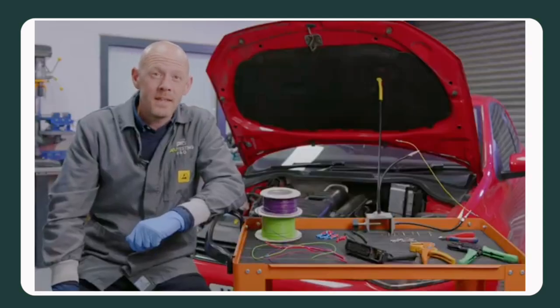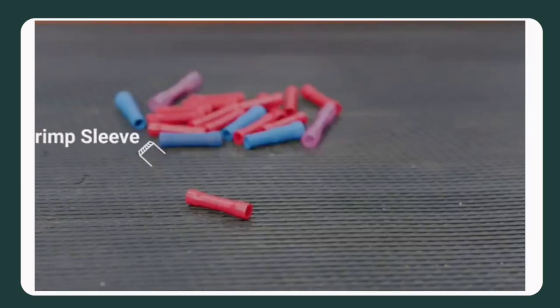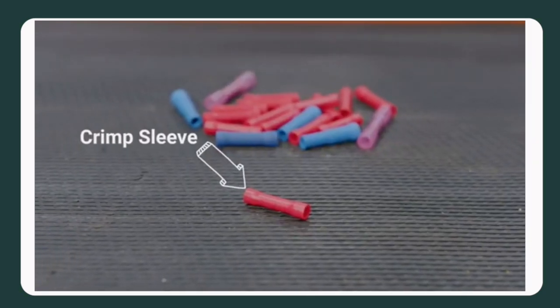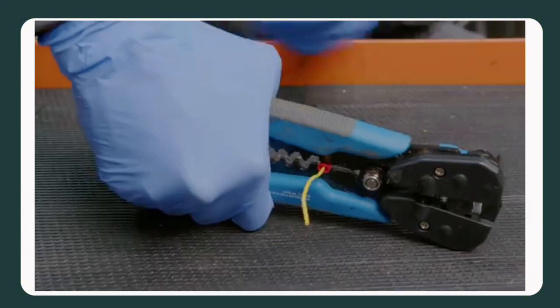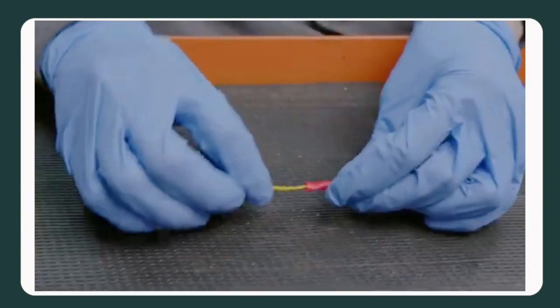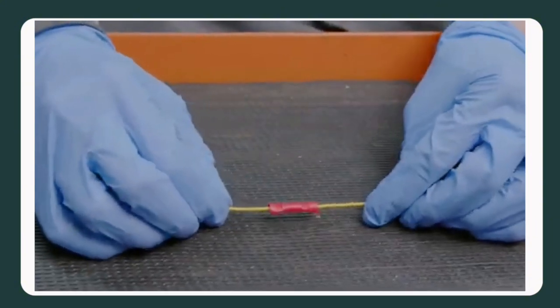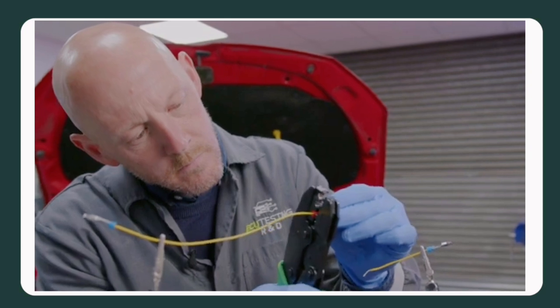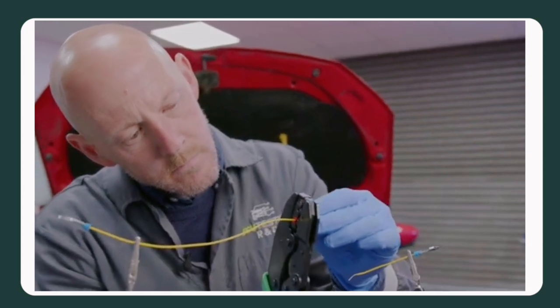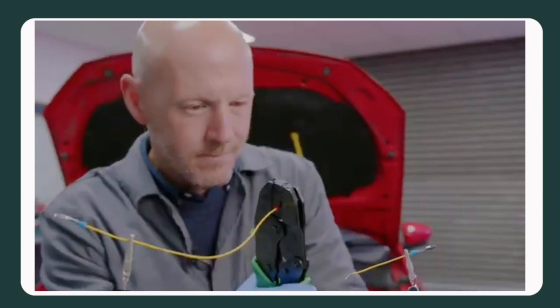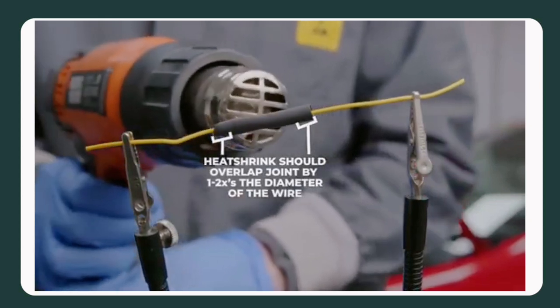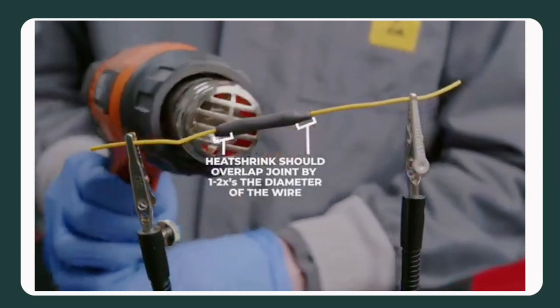Now this is where the methods of repair differ, and these can be affected by the amount of slack you have with a wire or the space you are working with. A crimp sleeve is the easier method of repair as they are straightforward to use and provide more slack to a wire. The two important things to remember when using these are: 1. Use a good crimping tool such as a ratchet crimper to ensure the connection is solid and even, and 2. Always use a heat shrink cover as a crimp sleeve isn't weatherproof.